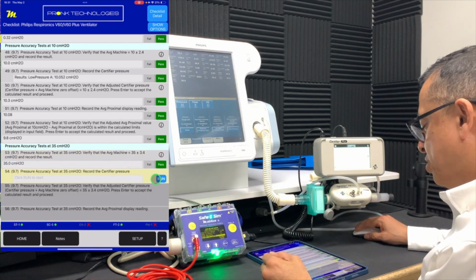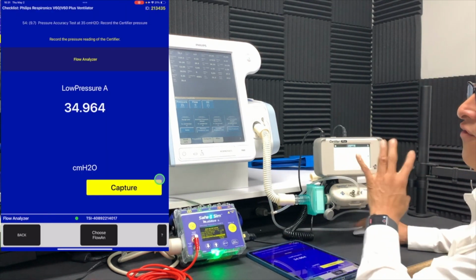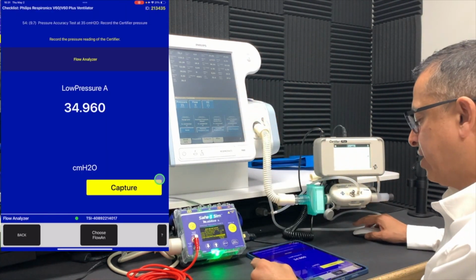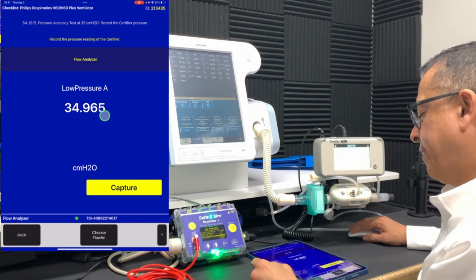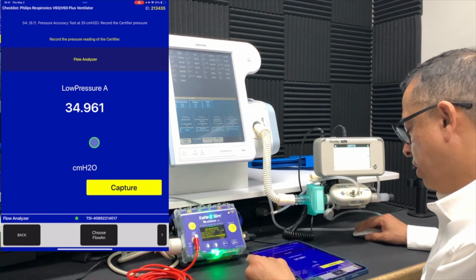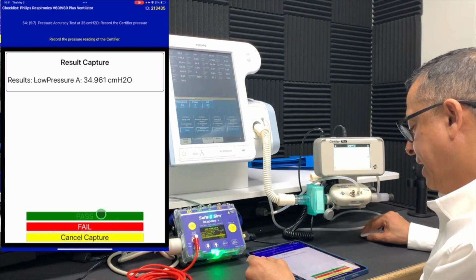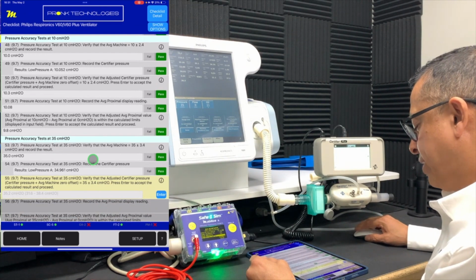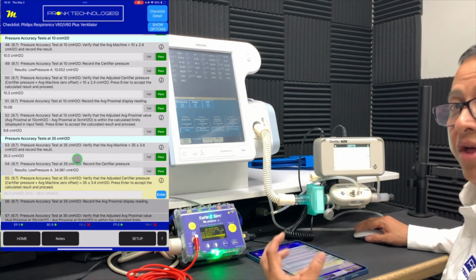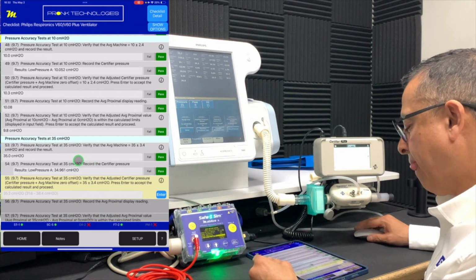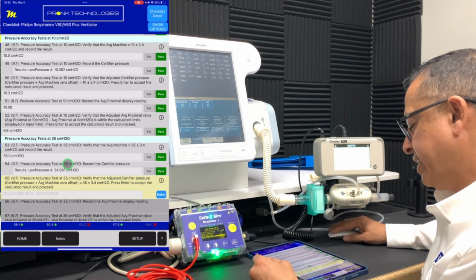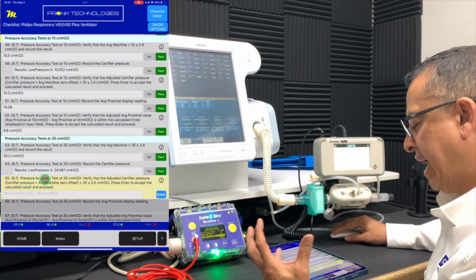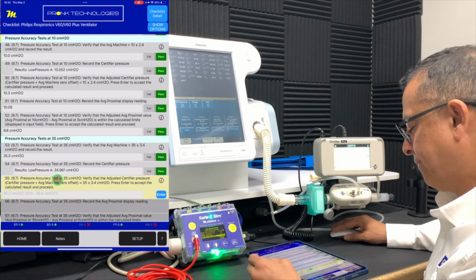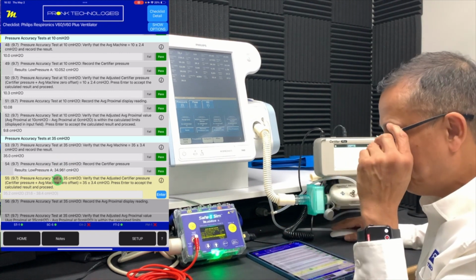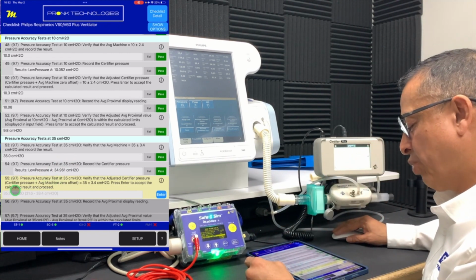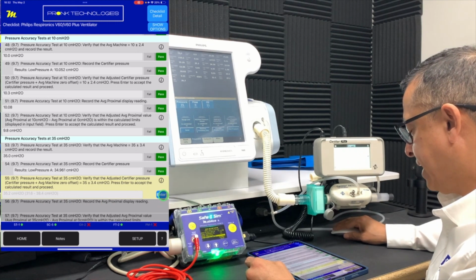And now we need to capture the certifier, of course. We need to have a reference to what the ventilator is displaying and confirm that result. Here's what the certifier is displaying within range as well. That is a pass. We've captured that result. Yet here's another calculation that has to be done. This calculation is in reference to the certifier pressure plus average machine zero offset. It has to be within a particular range. And you can see here that it is well within that range. So we've accepted that result as well.